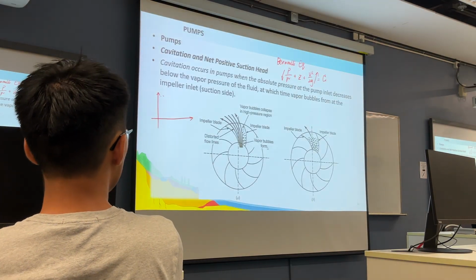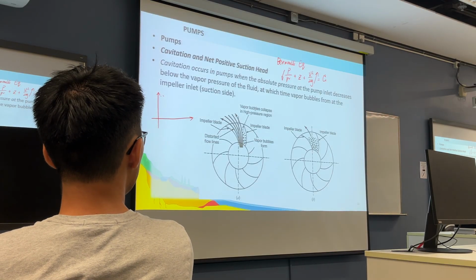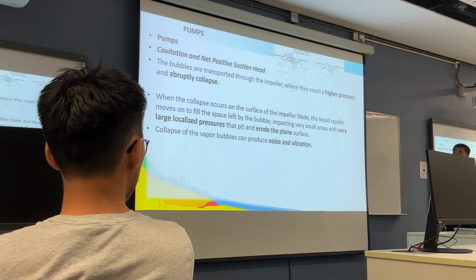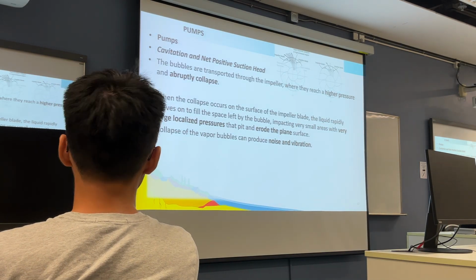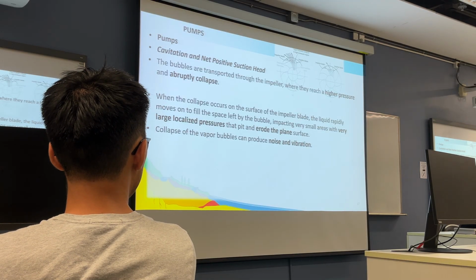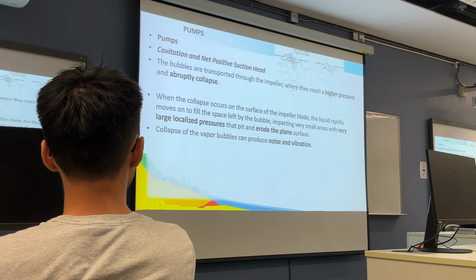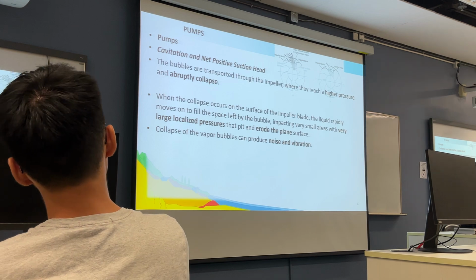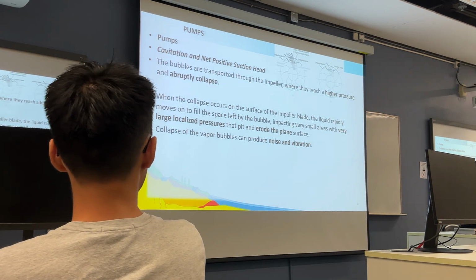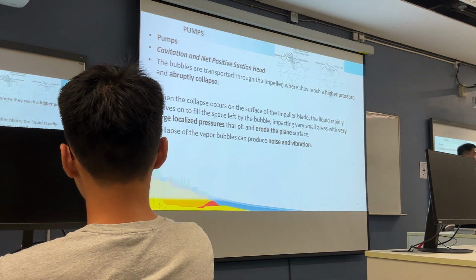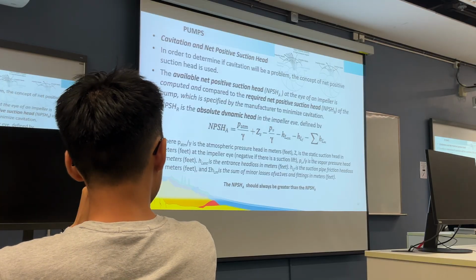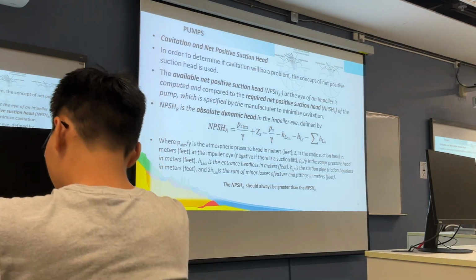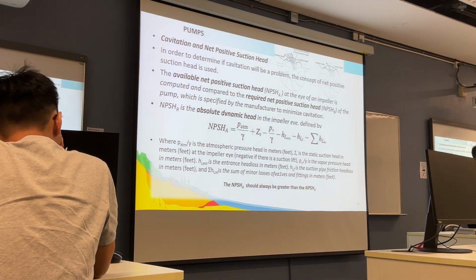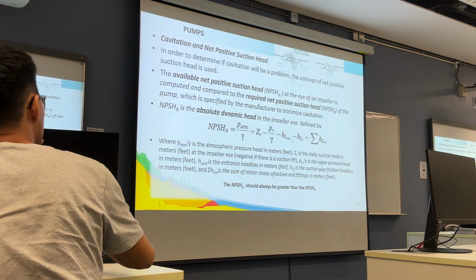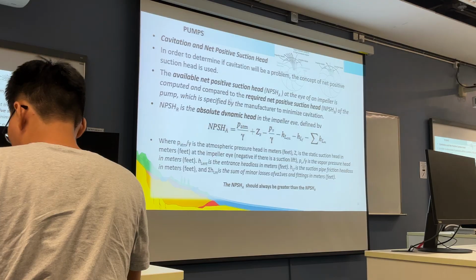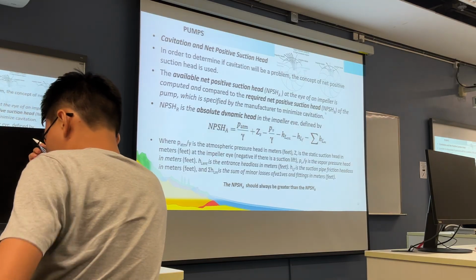Alright, so this is the so-called cavitation. The cavitation will damage the impeller. So for the design of the water pump head, the pump station, we need to calculate some parameters to see whether the pump setup is correct, to eliminate the pump cavitation effect. Then we will calculate the available net positive suction head, NPSHA, at the eye of the impeller, and compare it to the required net positive suction head, NPSHR.